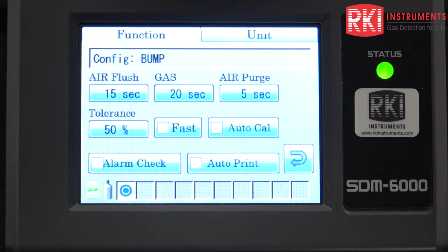The fast pretty much just means that within the first 10 seconds of this bump test, if it's within that tolerance that you entered, it's going to pass that bump test. It saves the gas. That's the main point of that.